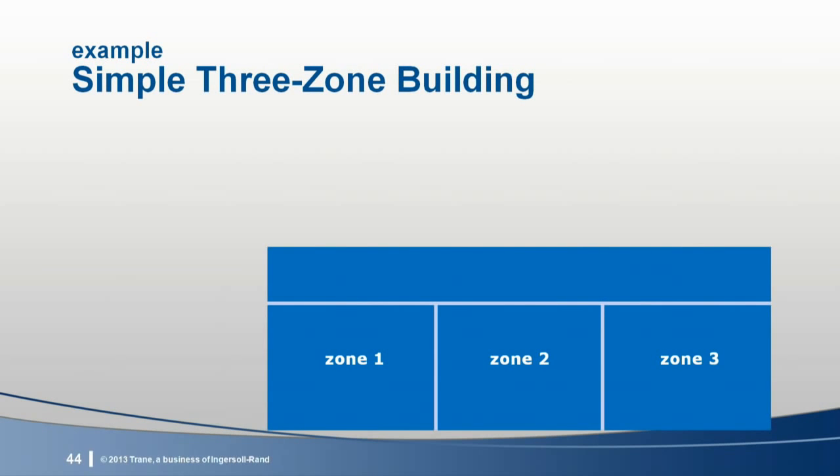To demonstrate the procedures for calculating system level intake flow, we'll use this very simple 3-zone example. As I mentioned, for each of the 3 configurations, the system calculations build off of the exact same zone calculations. So for our example, the zone outdoor airflows have already been calculated to be 300 CFM for zone 1, 400 CFM for zone 2, and 500 CFM for zone 3. We'll demonstrate the system calculations assuming operation in cooling mode. So zone air distribution effectiveness is equal to 1 in each zone, but I will mention how the results might change in the heating mode later on.